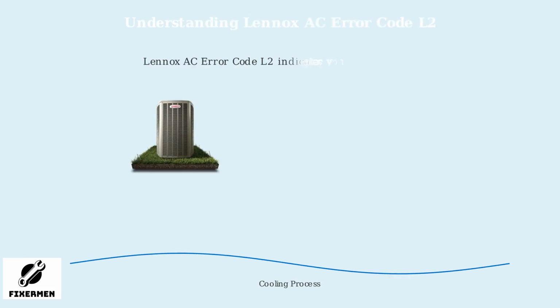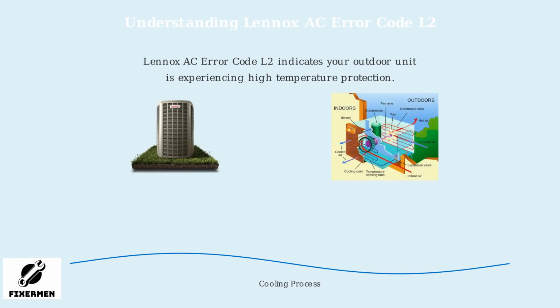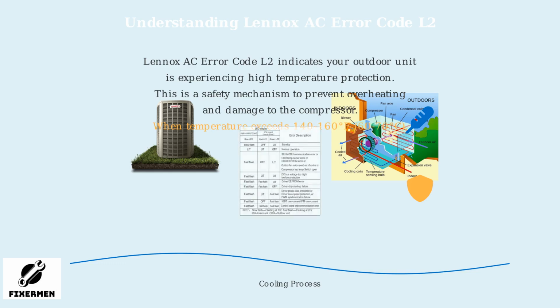Lennox AC Error Code L2 indicates that your outdoor unit is experiencing high temperature protection. This is a safety mechanism designed to prevent overheating and potential damage to the compressor and other critical components. When the outdoor unit's temperature exceeds a safe threshold, typically between 140 to 160 degrees Fahrenheit or 60 to 70 degrees Celsius, the system shuts down and displays the L2 error code.